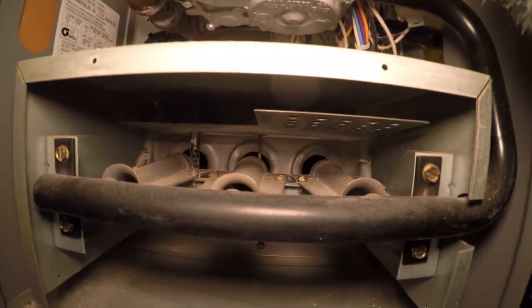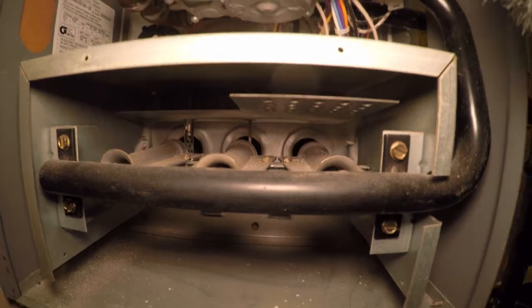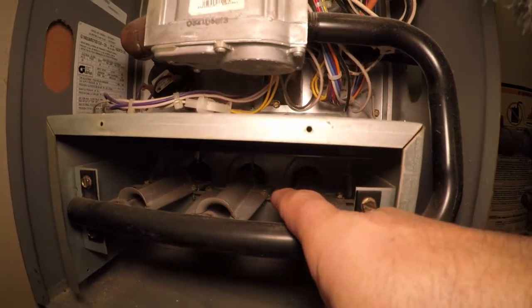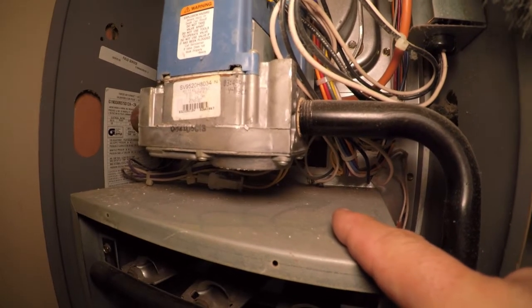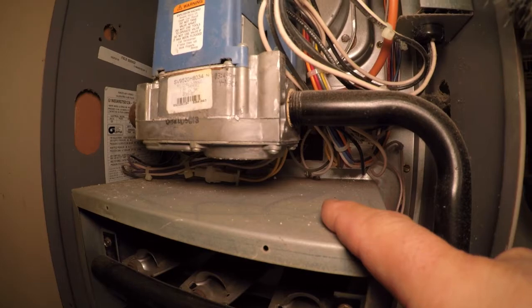So this is an Armstrong furnace, also branded as an AirEase. The flame sensor is located right back there, and the screw for that is right there. I'm going to go ahead and test that real quick, and we'll see what the signal is, and then we'll clean it.